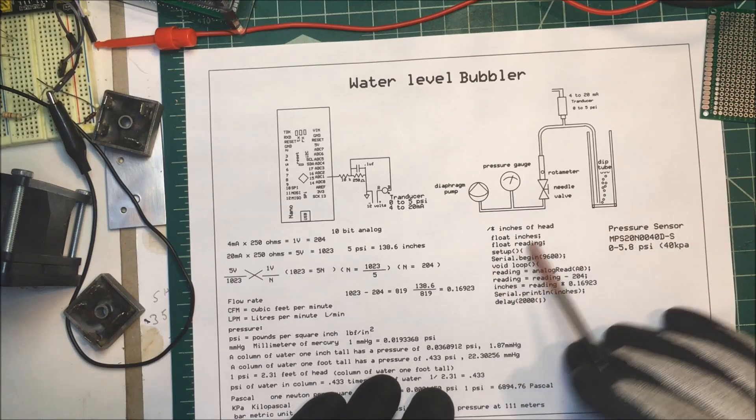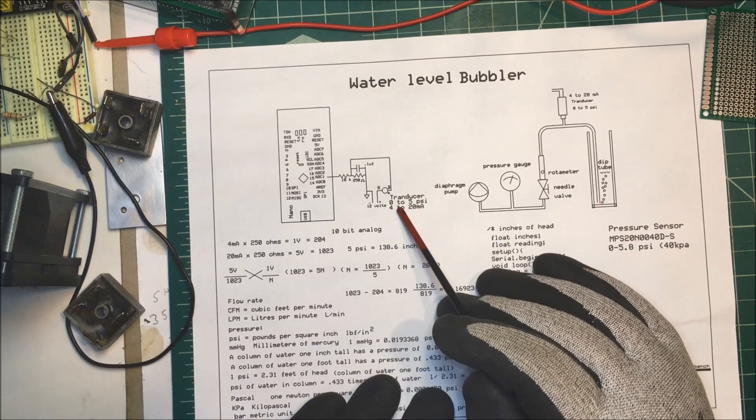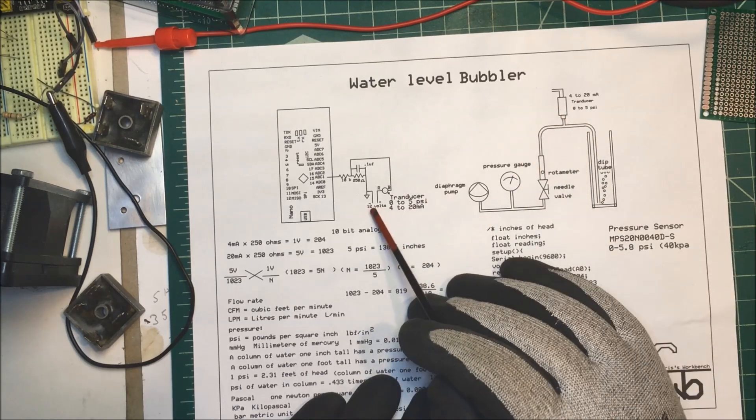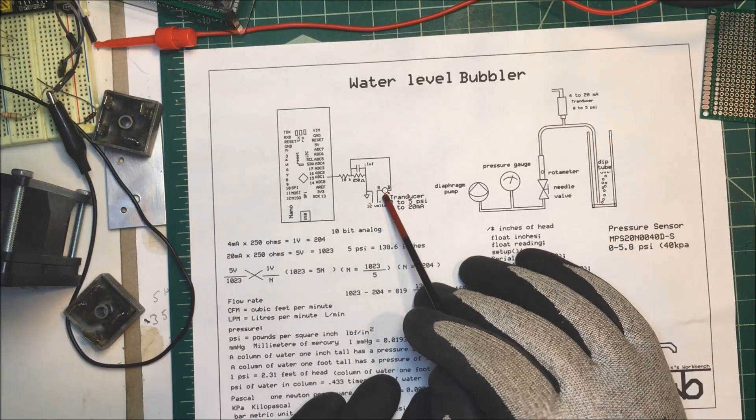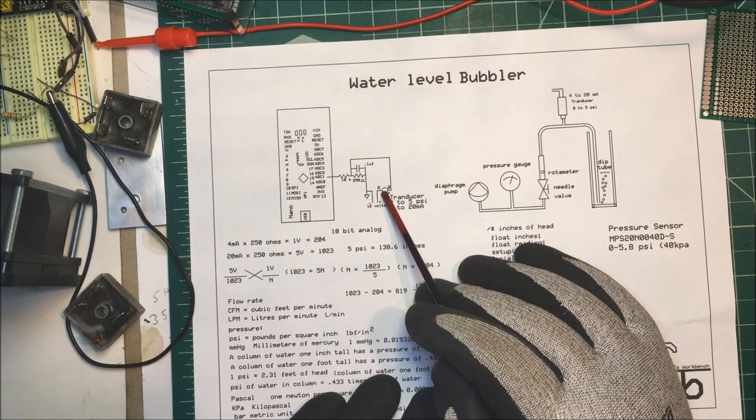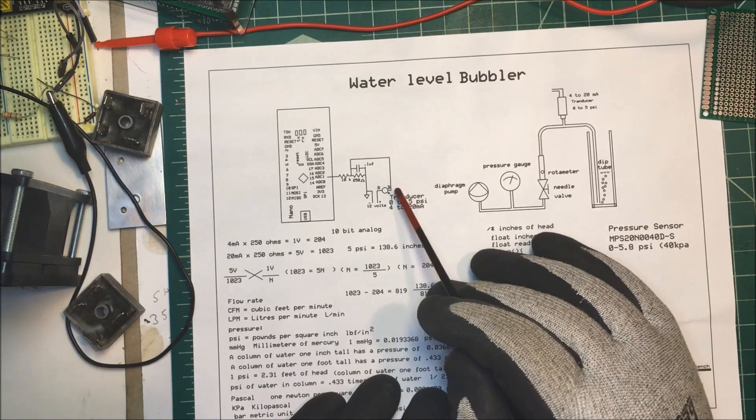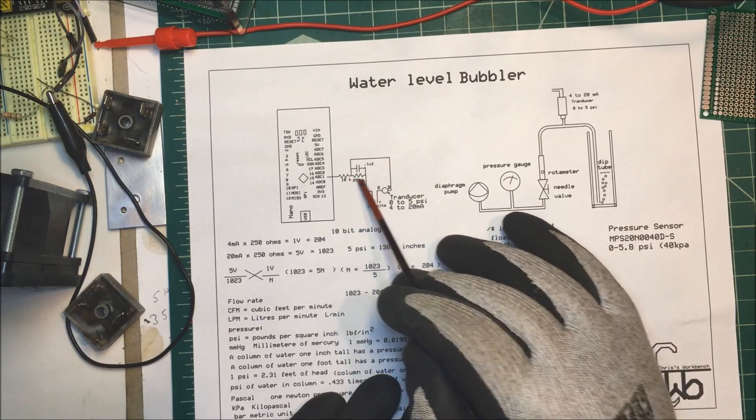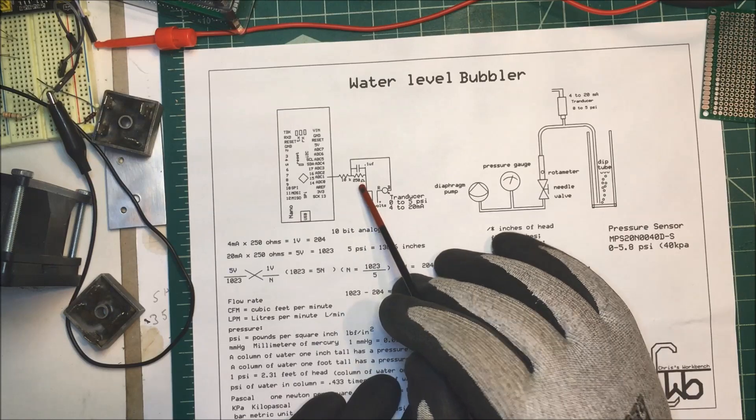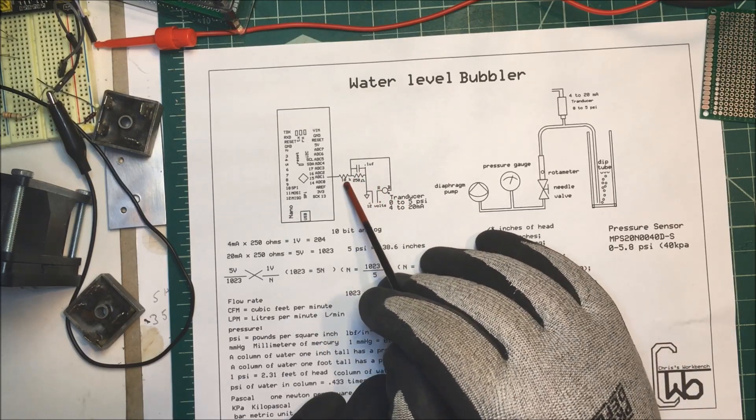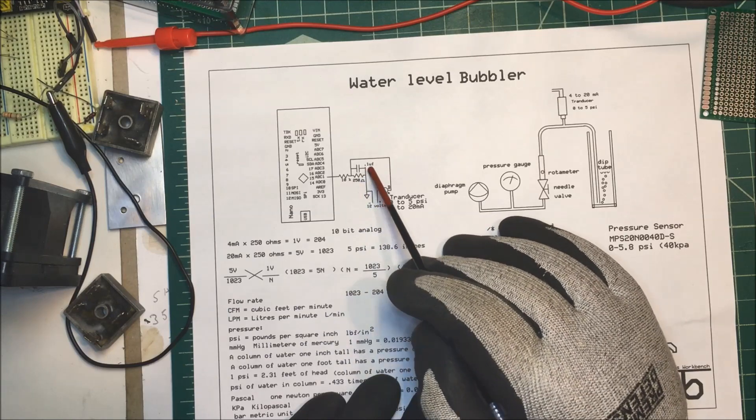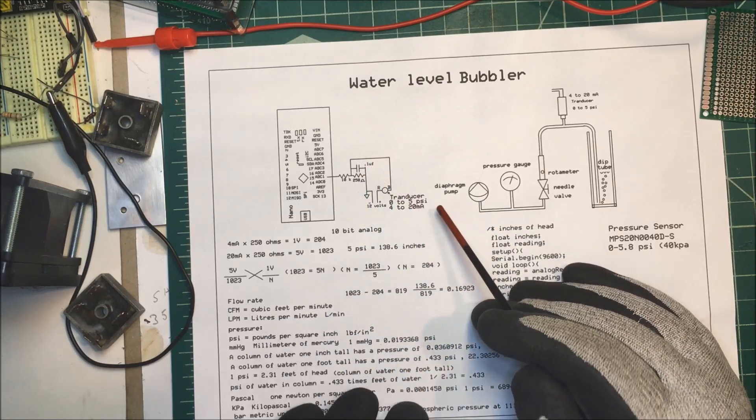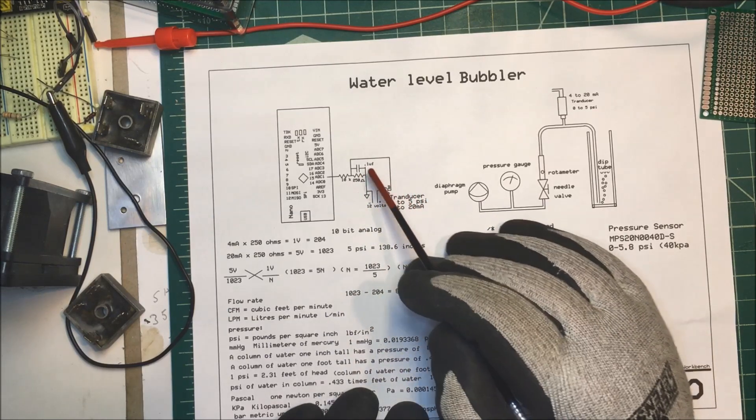Now, for our transducer over here, these run off of 12 volts. So I'm putting 12 volts into the positive, into the red lead on the transducer. And then out of the other side of the transducer, I go across the 250 ohm resistor here. And then we have a 10k here just to limit the current and a little capacitor across there just to smooth it out a bit.